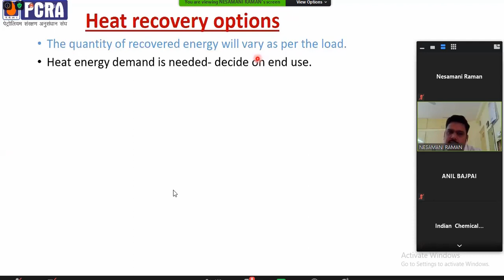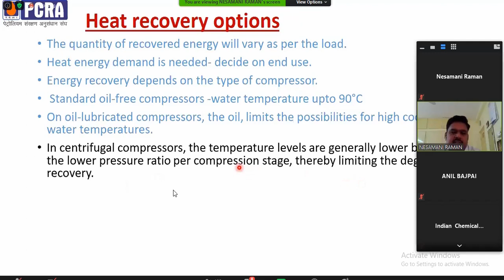The heat recovery quantity will also vary as per the type of compressor. Standard oil-free compressors are best suited for applying these heat recovery options because they generate water temperatures of up to 90 degrees Celsius, which can be used as boiler feed water or for any other purpose. In oil lubricated compressors, the oil takes away some heat, so it limits the possibility of heat recovery and water temperatures. In centrifugal compressors, the temperature levels are generally lower because the pressure ratio in each stage is lesser. So it will limit the degree of heat recovery.